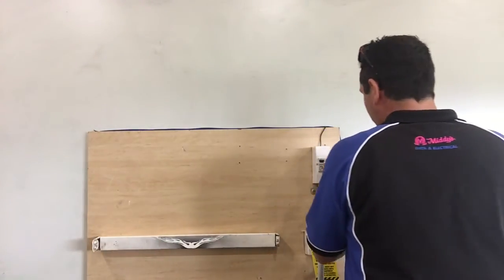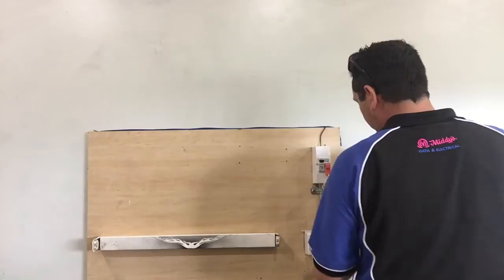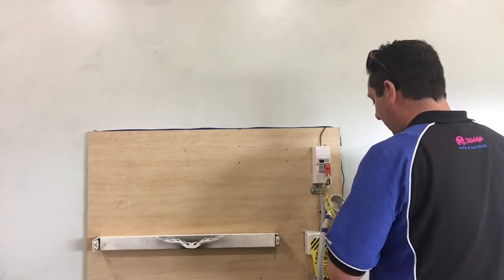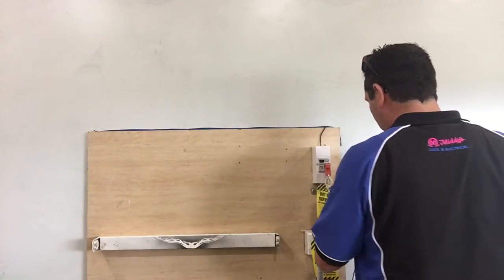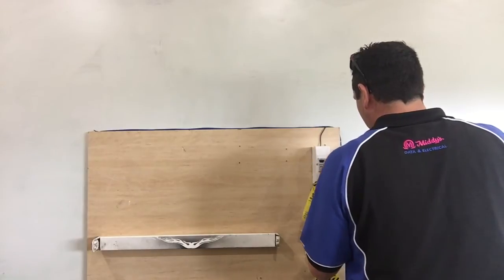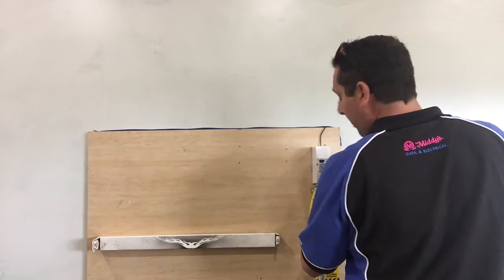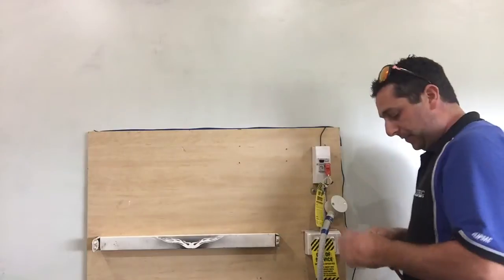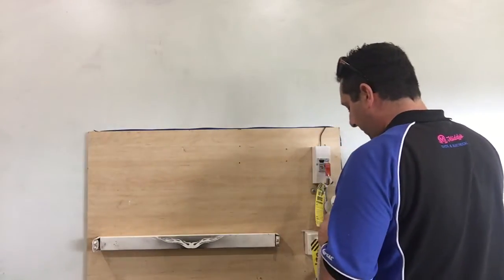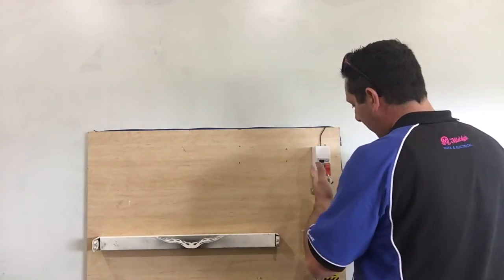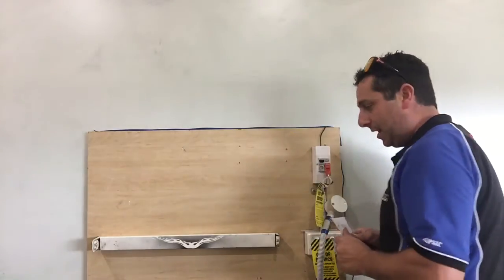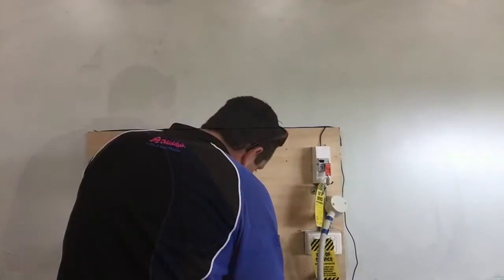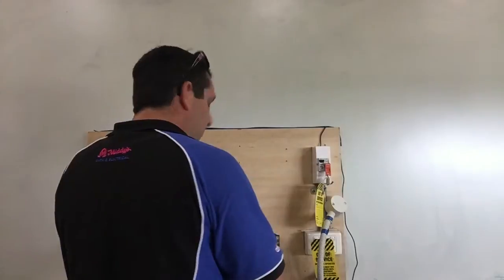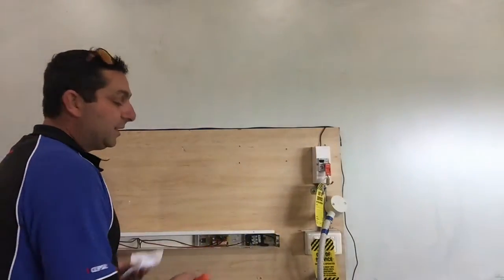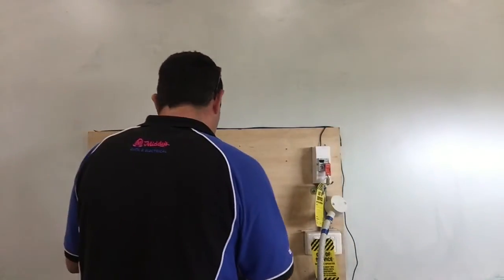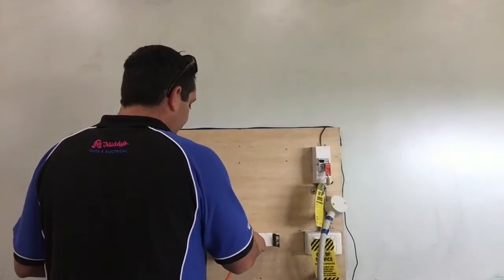What I like to do now is just get our diagram out, just so we can have a look at the switchboard and the appliance and make sure it's been replaced or repaired with exactly what it needs to be. So we can check our diagram. Yes, the switchboard looks fine. Yes, it looks like the same circuit. And the appliance, have a look. The appliance has been repaired, or if it's been replaced, it's been replaced with something that's like for like. Okay, so we've established that, and that all looks good.